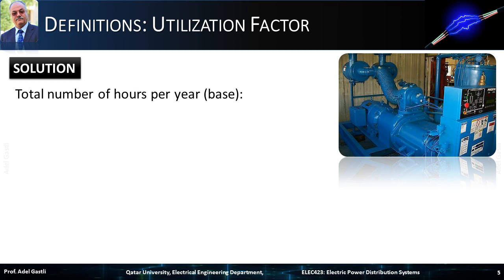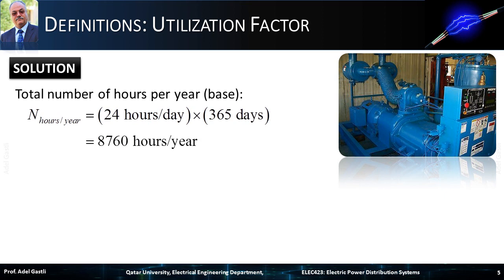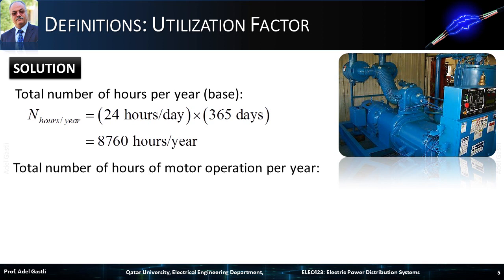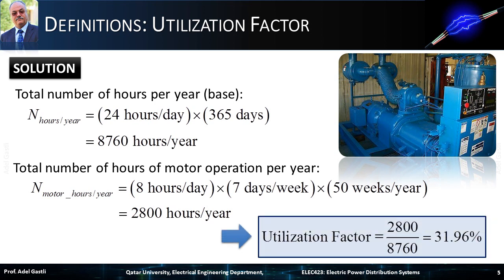To calculate the motor utilization or use factor on a yearly basis, we first determine the total number of hours in one year: 24 hours per day times approximately 365 days per year equals 8760 hours per year. The motor operates only 8 hours per day during 50 weeks of the year, so the total hours of motor operation per year is 8 hours per day times 7 days per week times 50 weeks, which is 2800 hours per year. Therefore, the utilization factor is 2800 divided by 8760, which equals 31.96%, meaning the motor is utilized on average only 31.96% of the total base time.